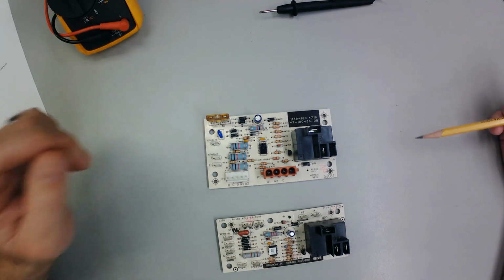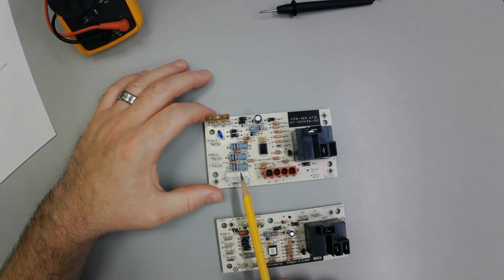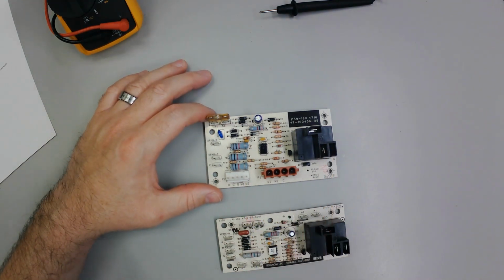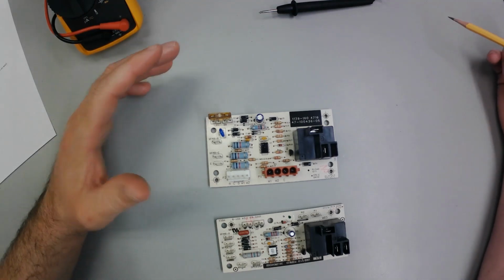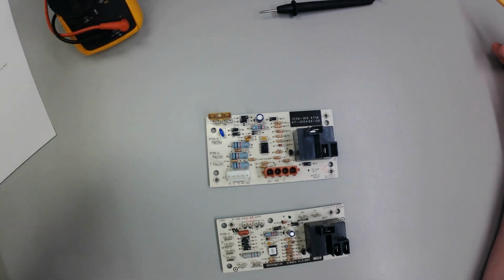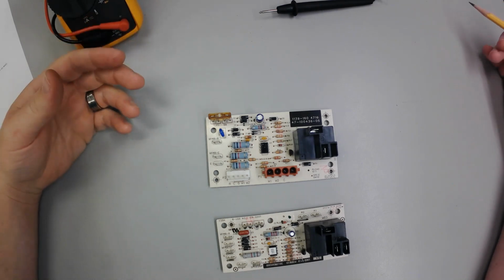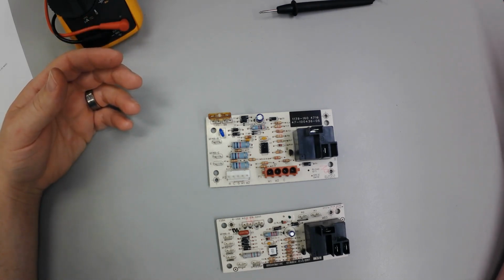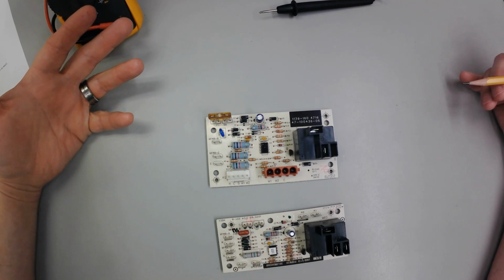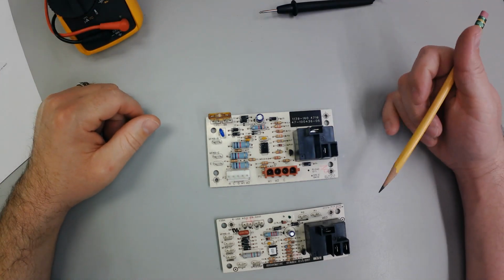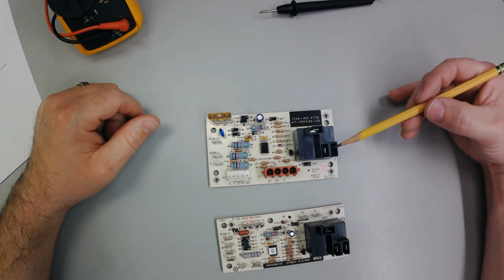You gotta like CSI this thing. Anytime I get a call for heat, I know to turn the fan on. We have to have airflow across our elements, otherwise we wind up tripping limits or fusible links, or God forbid we actually have something go wrong with the element. Point being, they're going to energize that fan no matter what. So that's the reason we don't have that.